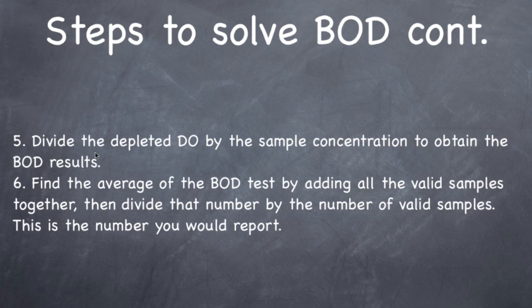Step 5: divide the depleted DO — take your initial, subtract the final, and divide that number by the sample concentration to obtain the BOD results. That number will be in milligrams per liter. Then find the average of the BOD test by adding all the valid samples together and dividing by the number of valid samples. So you'd add sample 1 plus sample 2 plus sample 3 and divide by 3. This is the number you would report to the state. So now we're actually going to solve a BOD problem.